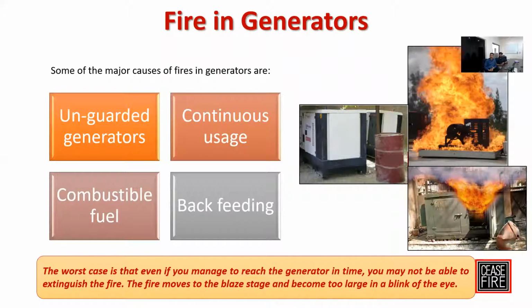You need to educate your customers - if any customers are part of this webinar, they should be aware that gensets do catch fire, and these fires could be deadly. They cannot be fought manually because it's very difficult to reach inside the canopy and into all the nooks and corners of the generator parts. So unless you have a complete protection system already installed inside the genset canopy, it is really very difficult to extinguish this fire.